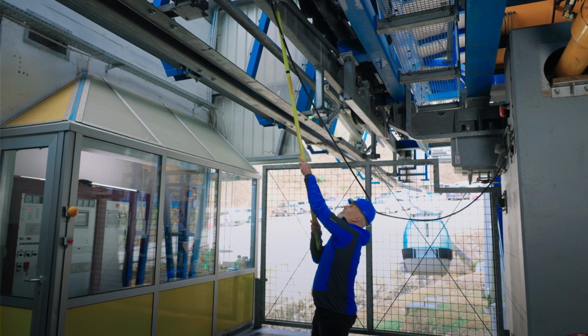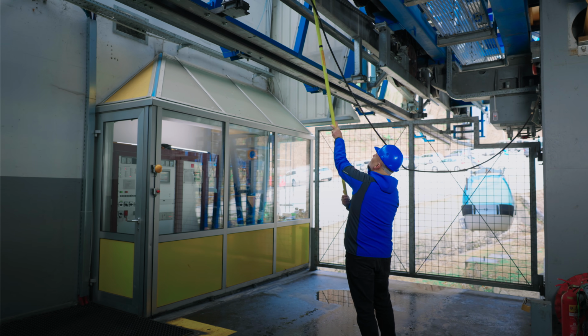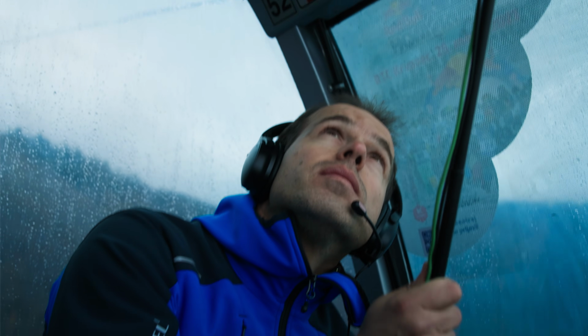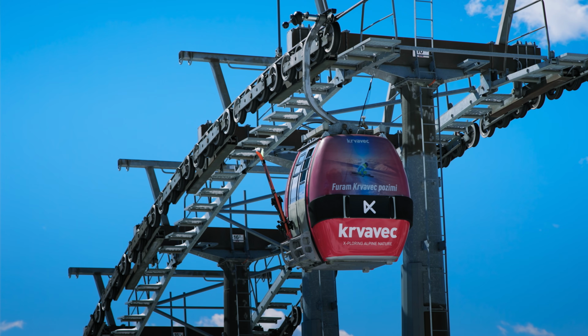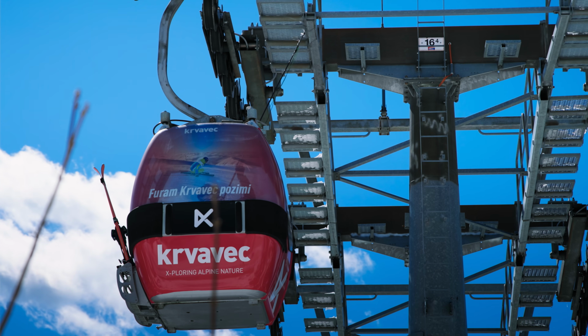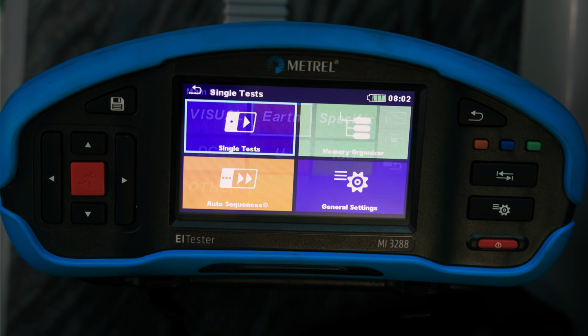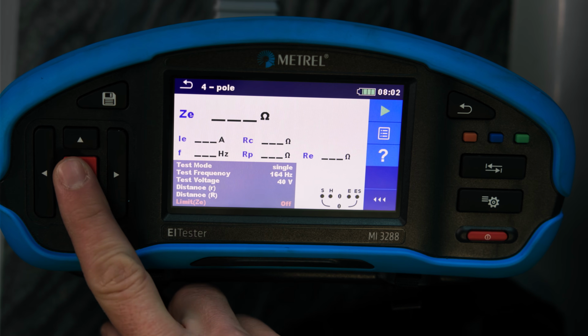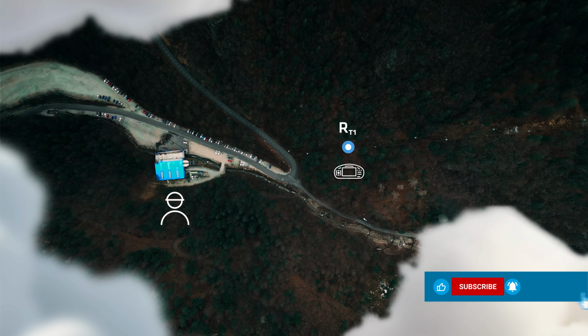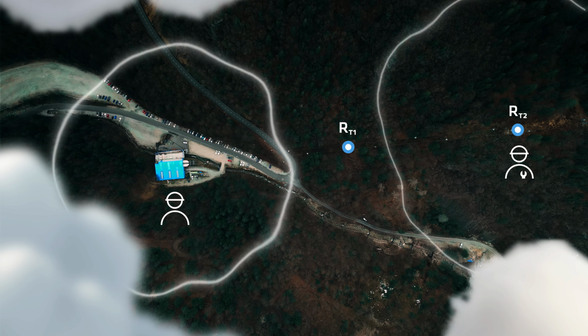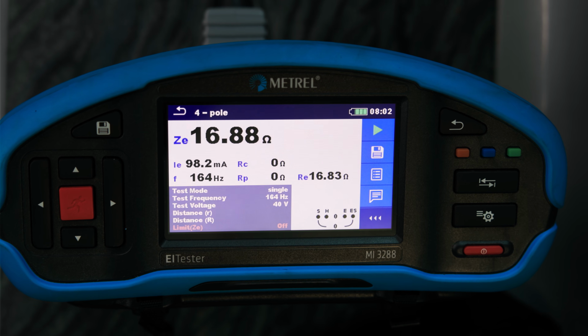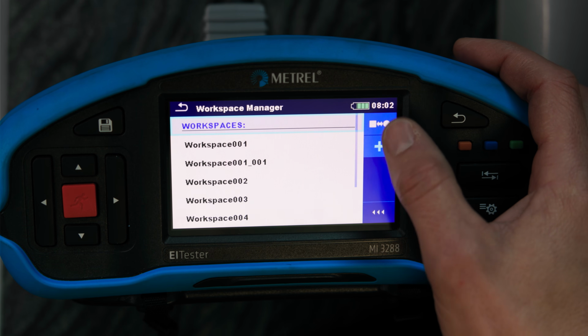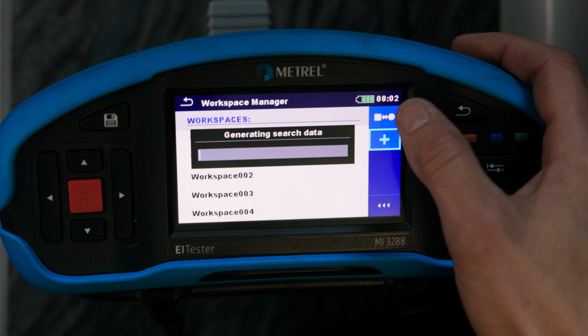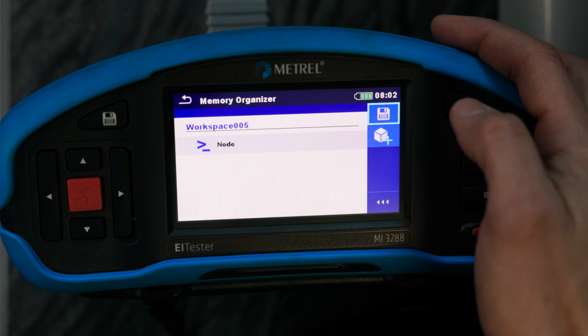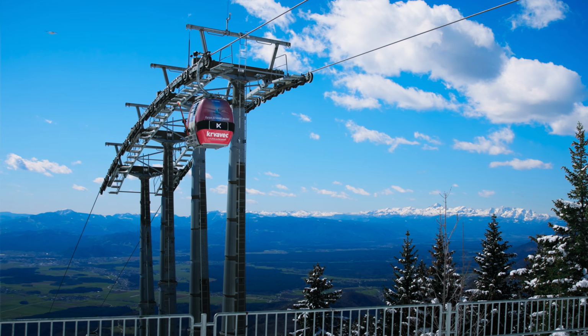During each stop, the operator grounds the system at the lower station. The inspector then uses an extension rod to make temporary contact with the tower's conductive structure. The MI3288 test creates a voltage funnel between the lower station and the local tower, measuring the combined resistance of both and saving results for later reporting. These steps are repeated at every tower until the job is complete.